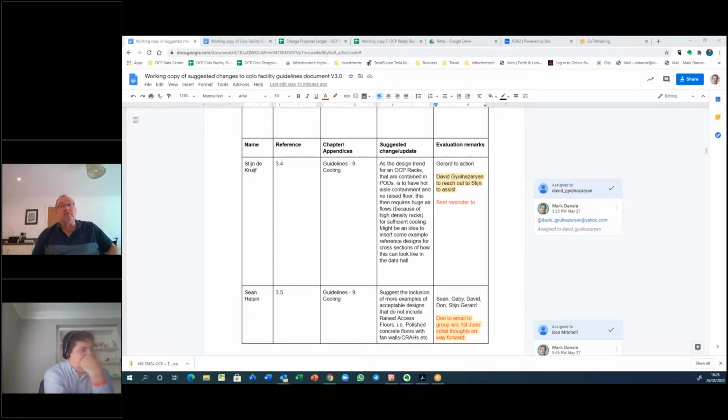If you look at the total power consumption, and then hopefully thus the airflow of a pod, is that good enough to understand what your aisle width might need to be? I think it certainly is enough to give guidance, and that's what I've been working around. But I think we'll probably have to have some caveat that individual studies may have to be run, or if a colo provider has got a model in CFD already prepared, they should consider perhaps spending X amount to simulate what their particular layout will be.